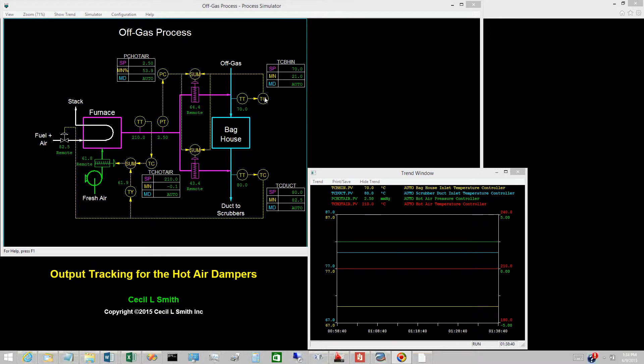The logic for when to track is as follows. Baghouse inlet temperature controller: tracking is active if either or both of the hot air dampers is on local. Hot air pressure controller: tracking is active if both hot air dampers are on local. This arrangement retains hot air pressure control preferentially to baghouse inlet temperature control, since the characterization function for the ratio of controls is strongly influenced by the hot air pressure.